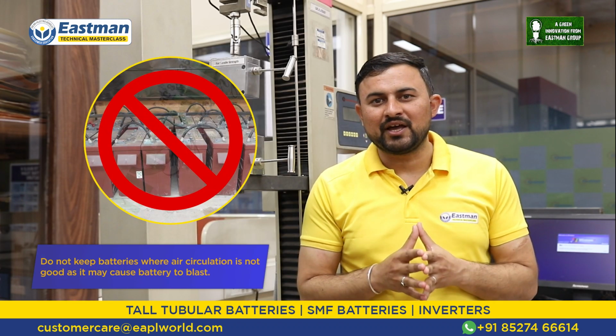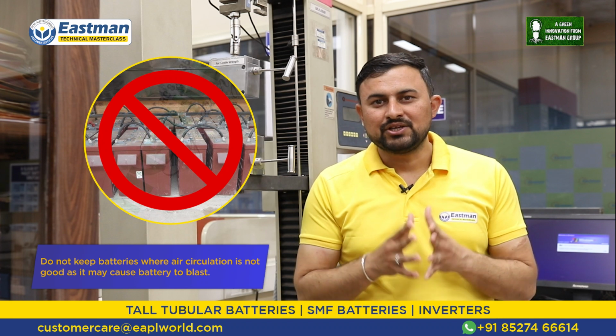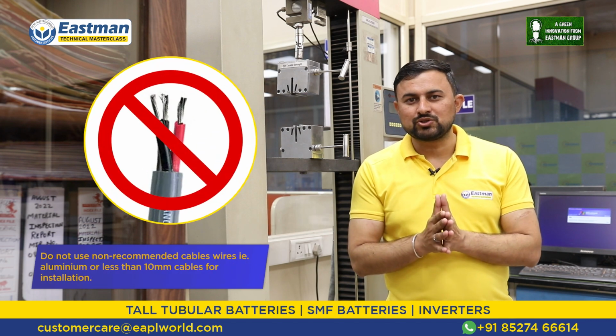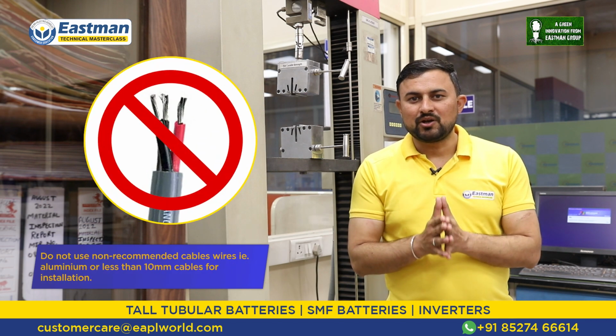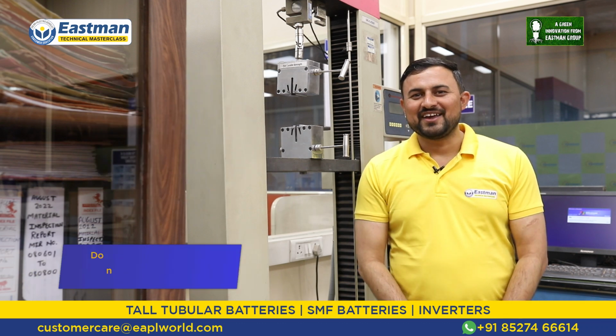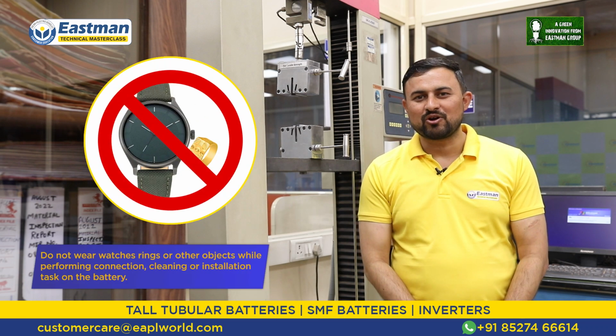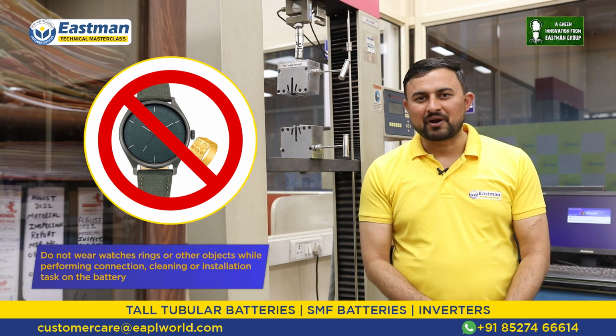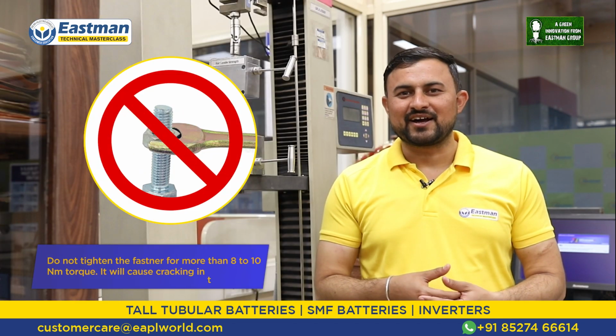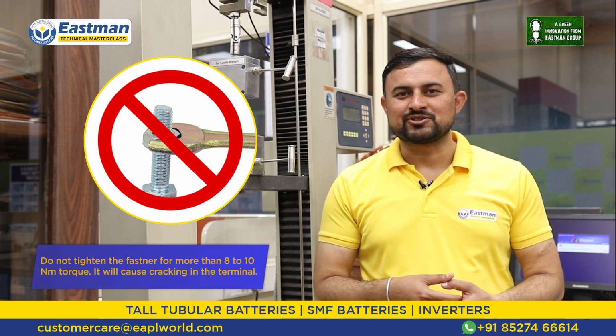Do not keep the battery where there is no proper air circulation. It increases the risk of a battery blast. Never use wire less than 10 square mm and never use non-recommended wire such as aluminum in your inverter. Do not wear any ring or wristwatch during connection, installation and maintenance of the battery at all. Do not over-tighten the fastener because it may cause terminal crack.